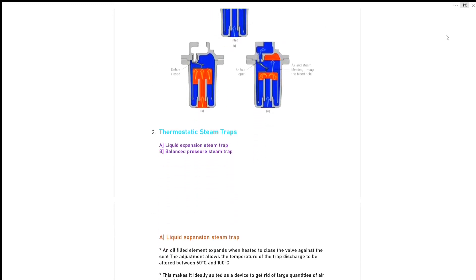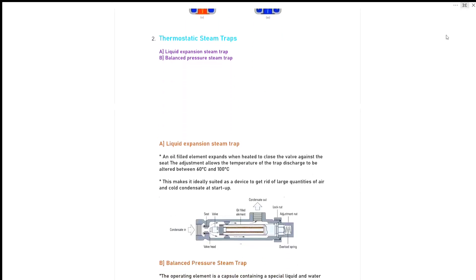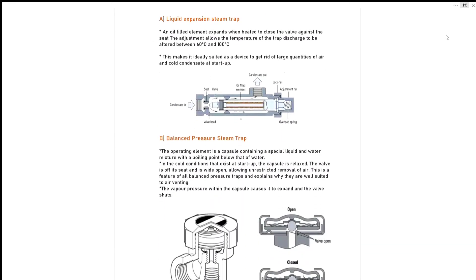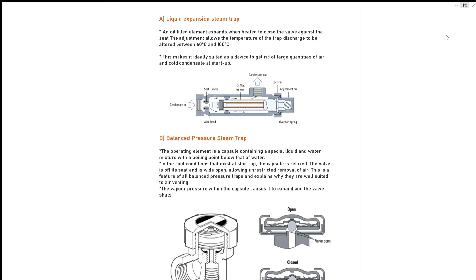Our second major type is thermostatic steam trap. It also has two types: one is liquid expansion steam trap and second is balanced pressure steam trap. Liquid expansion steam trap: an oil-filled element expands when heated, to close the valve against the seat. The adjustment allows the temperature of trap discharge to be altered between 60 degrees Celsius to 100 degrees Celsius. This makes it ideally suited as a device to get rid of large quantities of air and cooled condensate at startup.